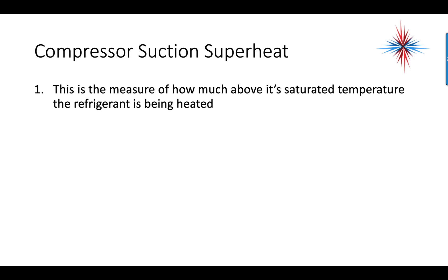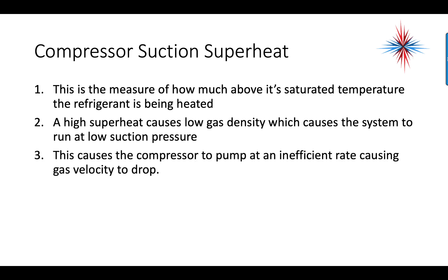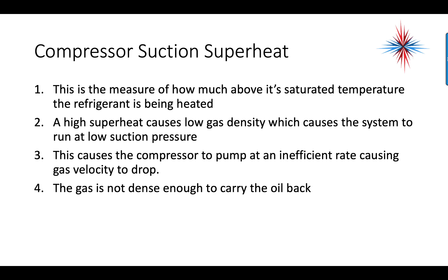We need to check the compressor's suction superheat — a measurement of how much above its saturated temperature the refrigerant is being heated. A high superheat causes low gas density, which causes the system to run at a low suction pressure. This causes the compressor to pump at an inefficient rate, causing the velocity of the refrigerant gas to drop. If the gas is not dense enough to carry the oil back, high superheat not only causes a heat issue and a loss of efficiency, it also causes insufficient oil return and will eventually damage the compressor.